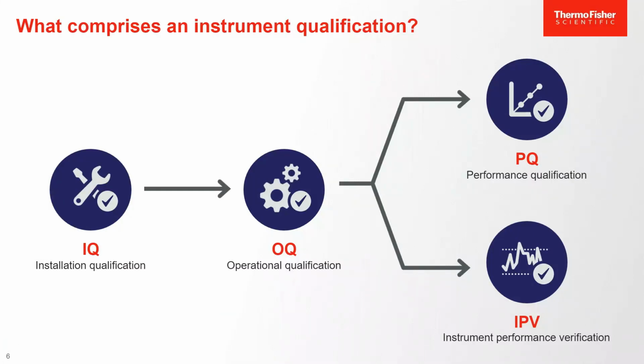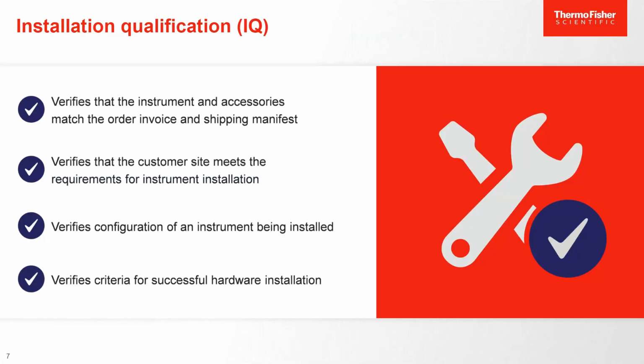What comprises an instrument qualification? First, we start with an IQ. IQs are installation qualifications. Next, you will move to an operational qualification. From there, you will branch from performance qualification to instrument performance verification. Let's start with installation qualification. This verifies that the instrument and accessories match the order invoice and shipping manifest. We also verify that the customer site meets the requirements for instrument installation. Some more steps that we take is verifying configuration of an instrument that is being installed. And we also verify the criteria for a successful hardware installation.